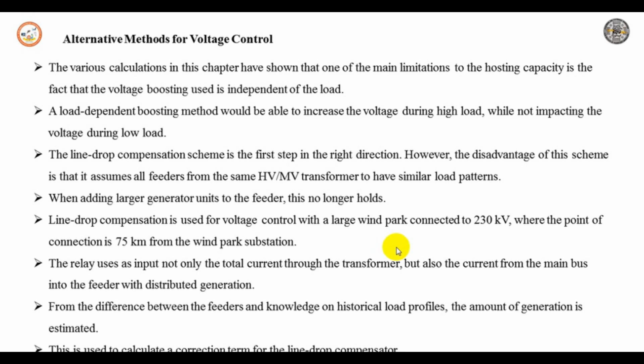The various calculations in these sessions have shown that one of the main limitations to the hosting capacity is the voltage boosting used, which is independent of load. The load-dependent boosting method would be able to increase the voltage during high load, while not having any impact on the voltage during low load. The line drop compensation scheme is the first step in the right direction.